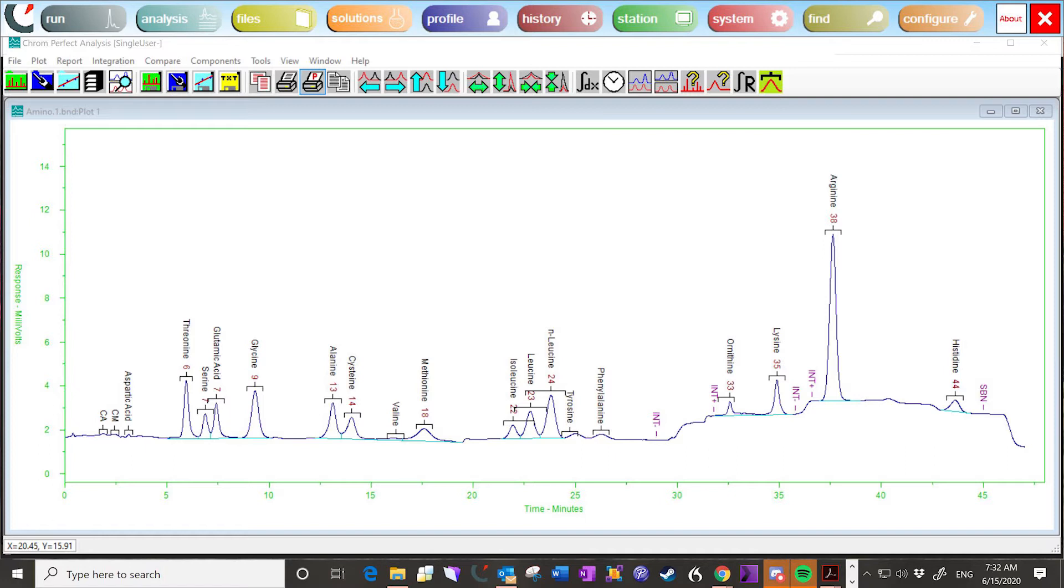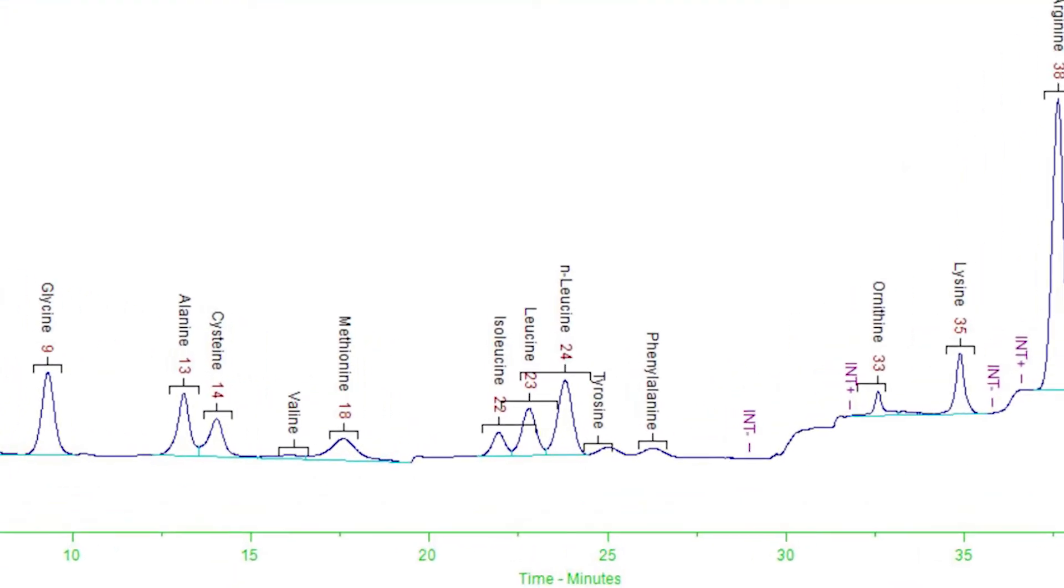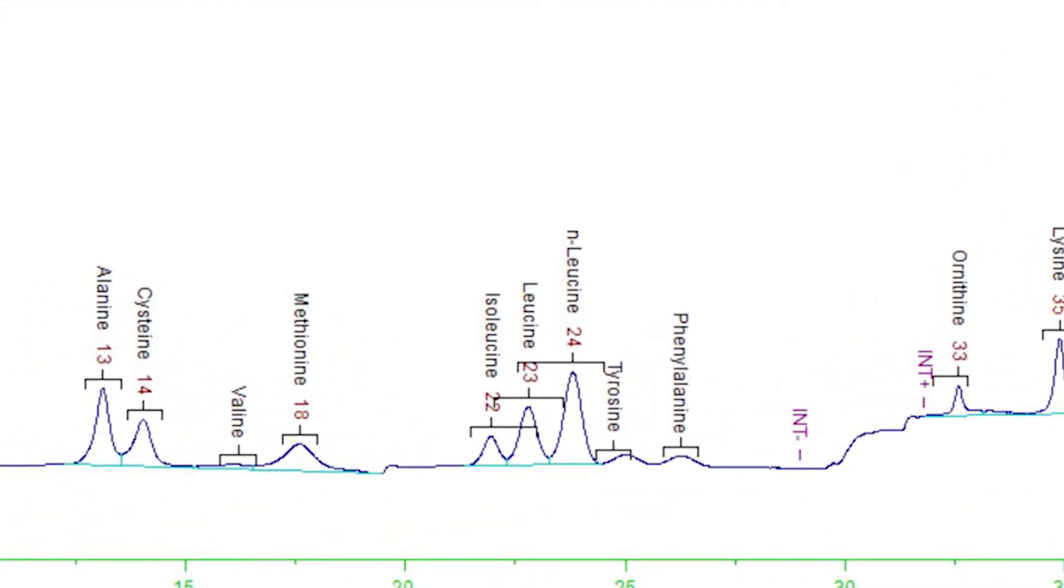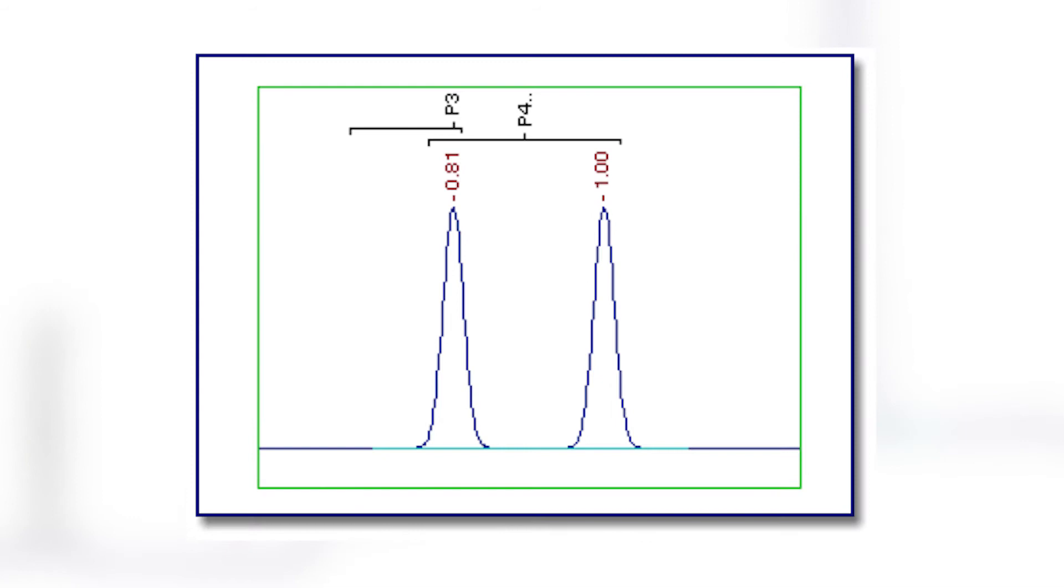Consider what happens when search windows overlap and a peak is tentatively assigned to more than one component. These conflicts must be resolved. Each component gets only one chance to find a peak. If a peak is tentatively assigned to more than one component, then the component that loses that peak will have no peak at all assigned to it, even if there was another peak under that window.